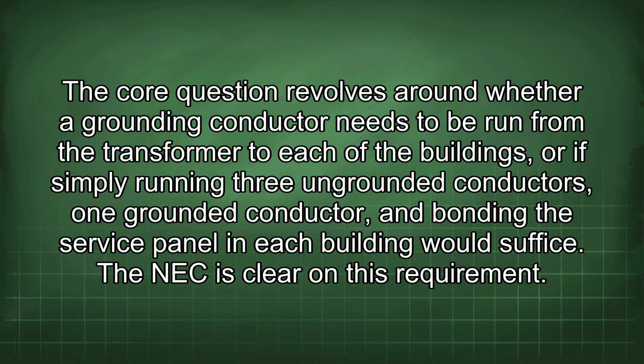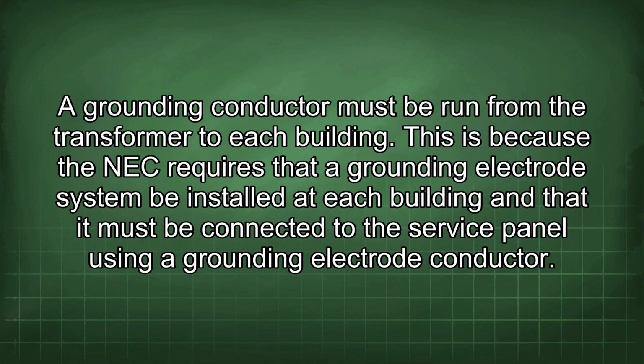The core question revolves around whether a grounding conductor needs to be run from the transformer to each of the buildings, or if simply running 3 ungrounded conductors, 1 grounded conductor, and bonding the service panel in each building would suffice. The NEC is clear on this requirement. A grounding conductor must be run from the transformer to each building.